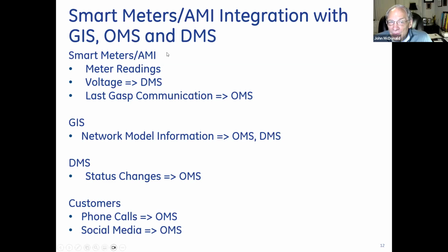So, we use smart meters for a number of things. They give us power quality information. They give us voltage information, which is very important because when we do volt-var control, we flatten the voltage profile and we lower it, but we need to make sure the voltage at the very last customer on the feeder is above the standard for our country. Like in the United States, it's 120 plus or minus 5%. So 120 minus 5% is 114 volts. We want to make sure that the voltage is well above 114 volts at the end of the feeder. So we can ping certain smart meters at the end of the feeder to get the voltage, okay? Good example of integration.